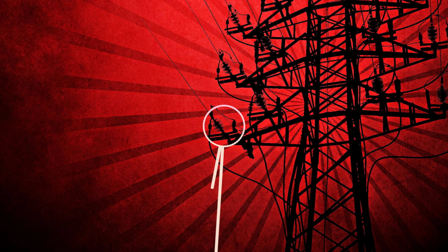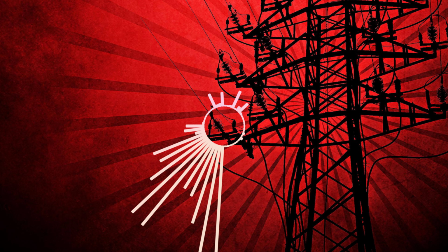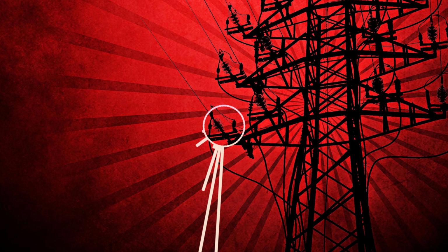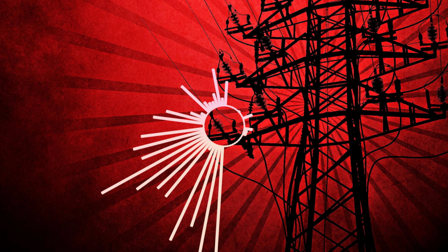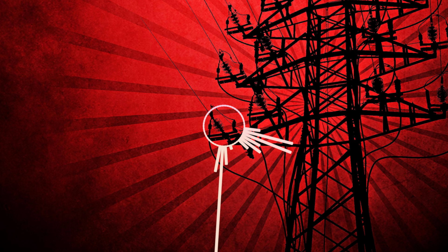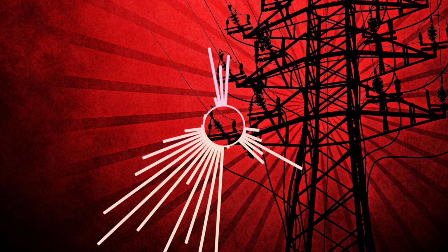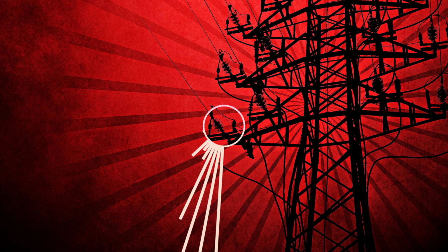According to the rule, you cannot use the wire's full 90 degrees Celsius rating because the equipment is only rated at 60 degrees Celsius. To comply with the NEC, you would have to adjust the ampacity of your 90 degrees Celsius wire to match the 60 degrees Celsius rating of the terminal.